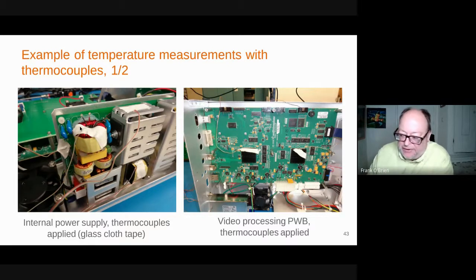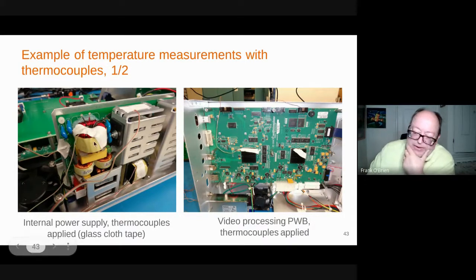But if the temperature gets anywhere near 130, which is what the tapes are rated for, you'll see, because you check the temperature every 15 or 10 minutes, you'll see the temperature maybe be very hot, and then all of a sudden it's less hot. And it's because the tape got loose. And you're also monitoring the absolute temperature as well. So you have to keep in mind that there's limitations to this method. But generally you're way under the limits for the tape. And so it's a very effective way to apply thermocouples. And you can quote me on that. But it's not in the CB guidance.